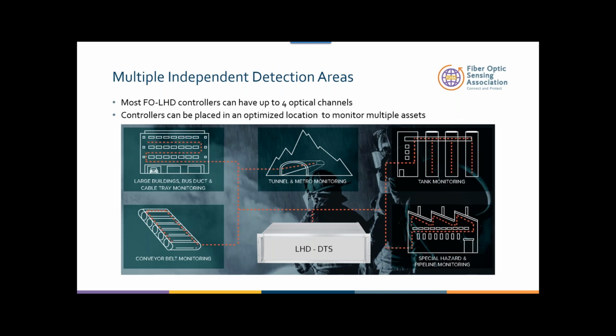The second advantage of the system is that most people have a linear heat detection system, fiber optic, which is a DTS, distributed temperature sensing, and most vendors have up to 4 optical channels. What that means is you can actually monitor multiple things at the same time with one controller. This controller can tie into your fire panel, which I'll talk about later on. So you can have a large building, you can have a bus duct, you can have a cable tray.